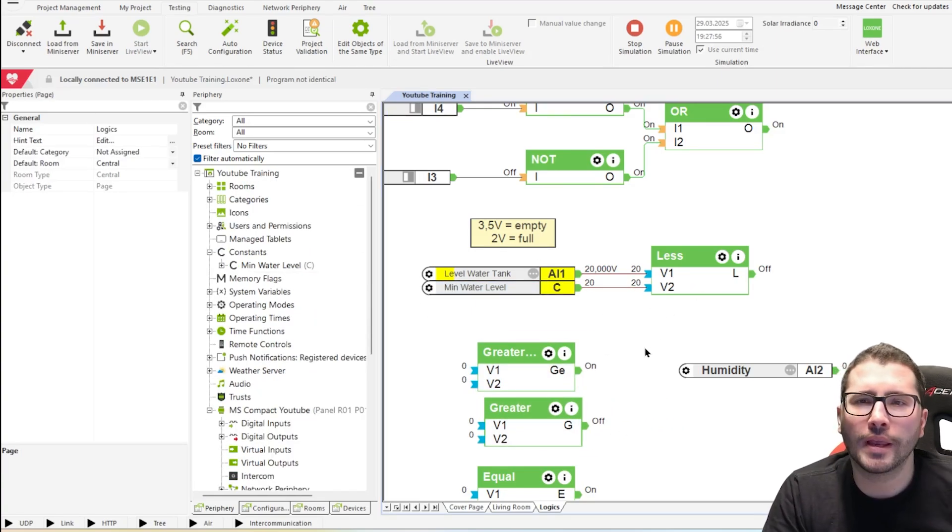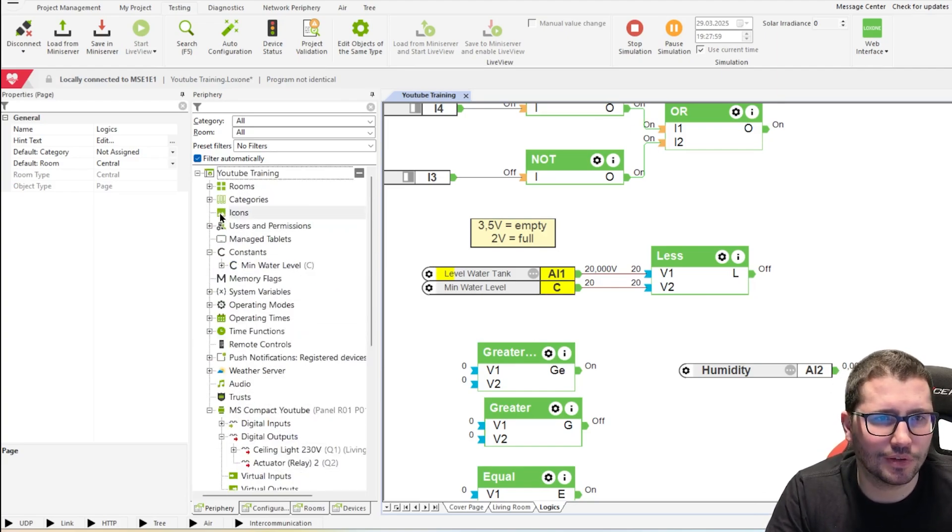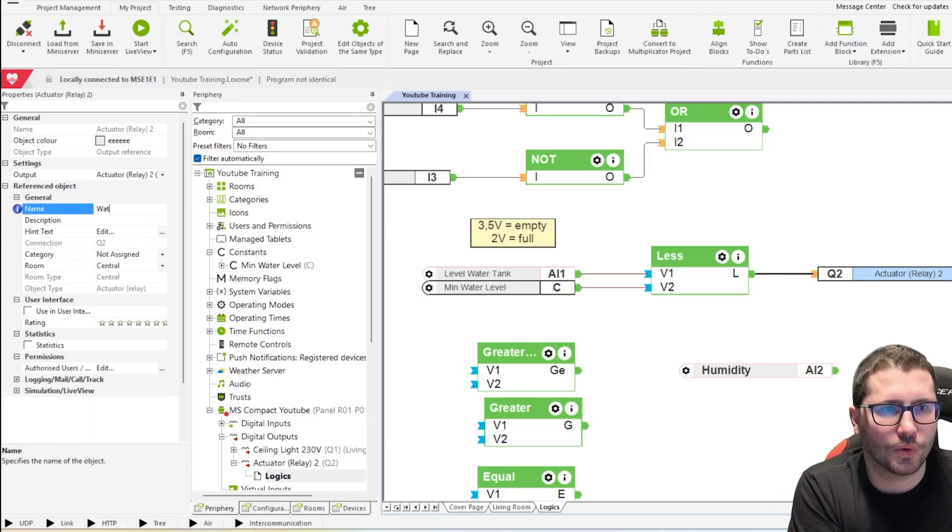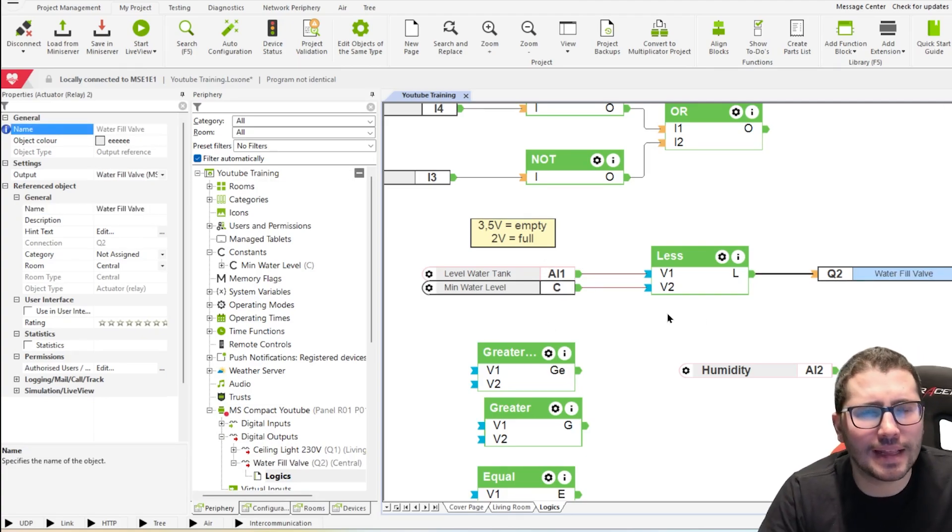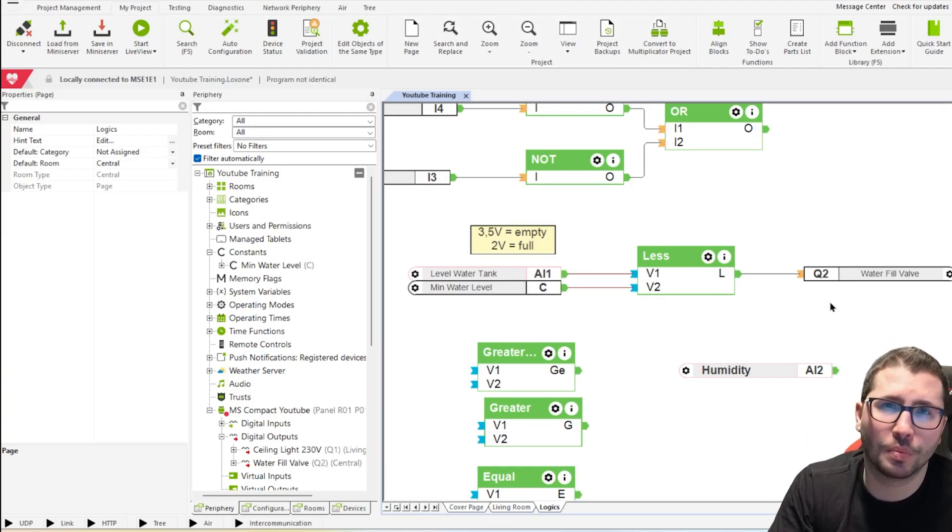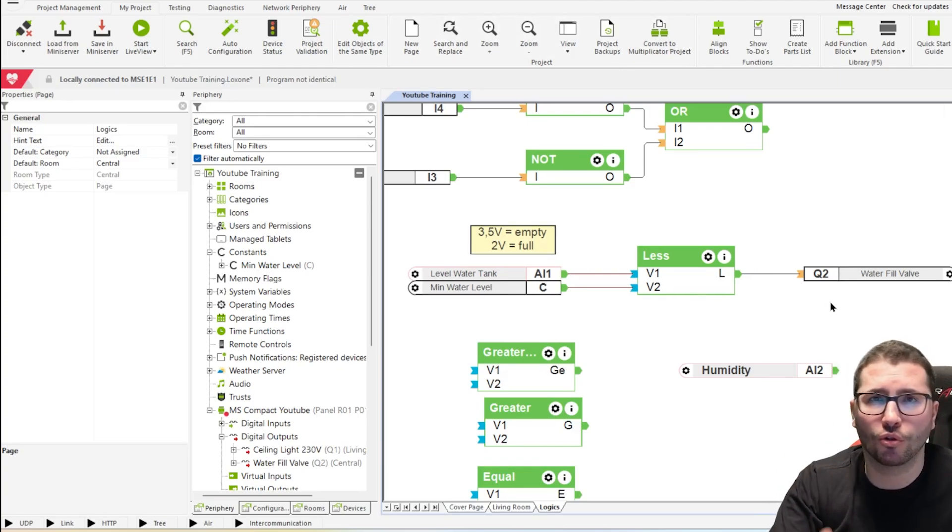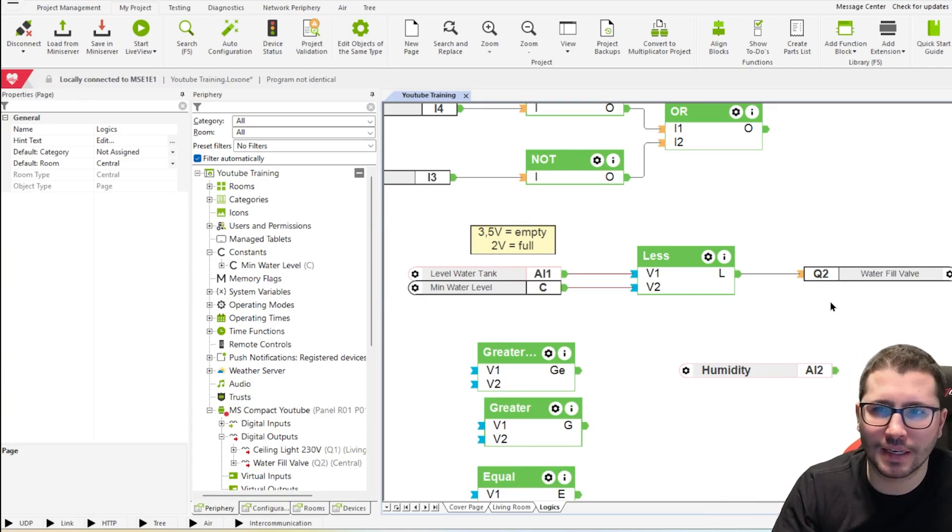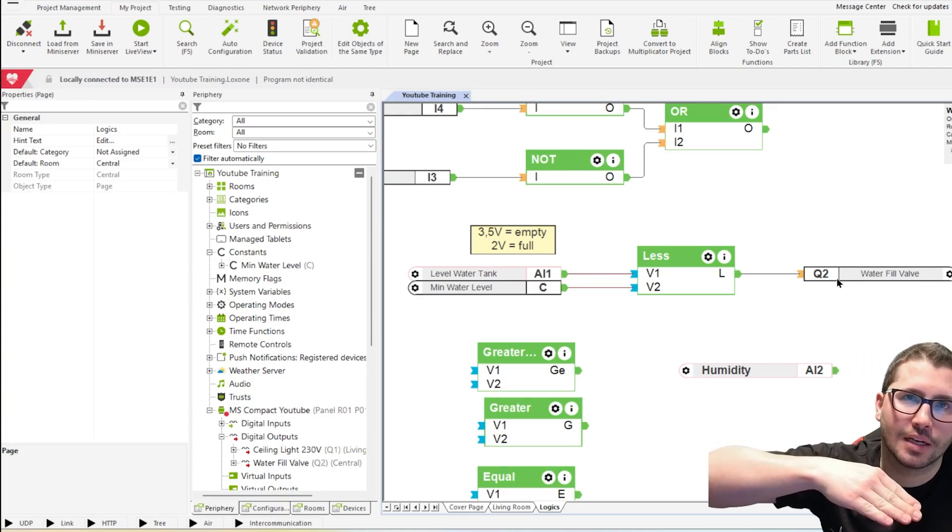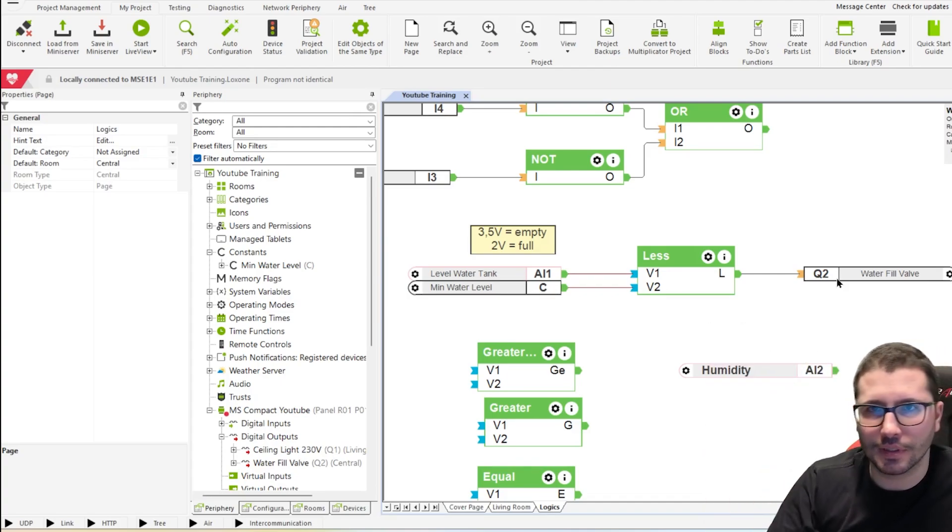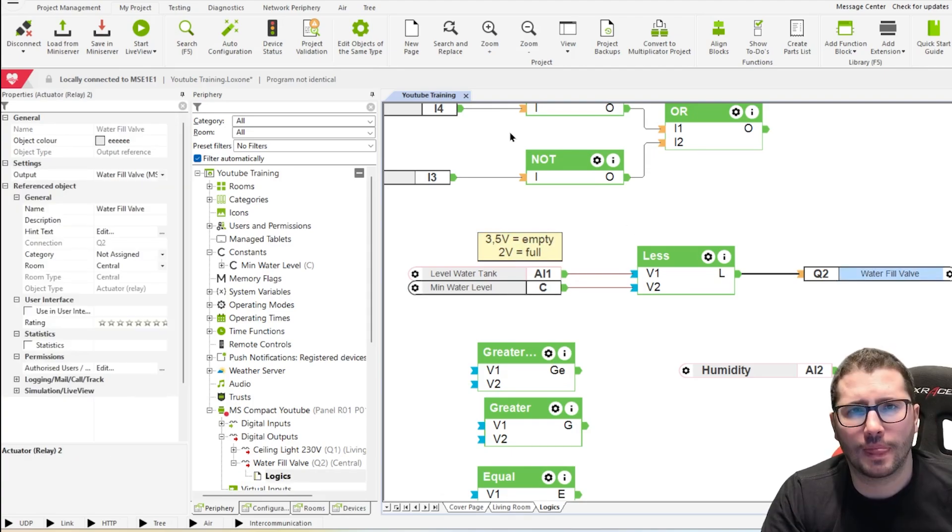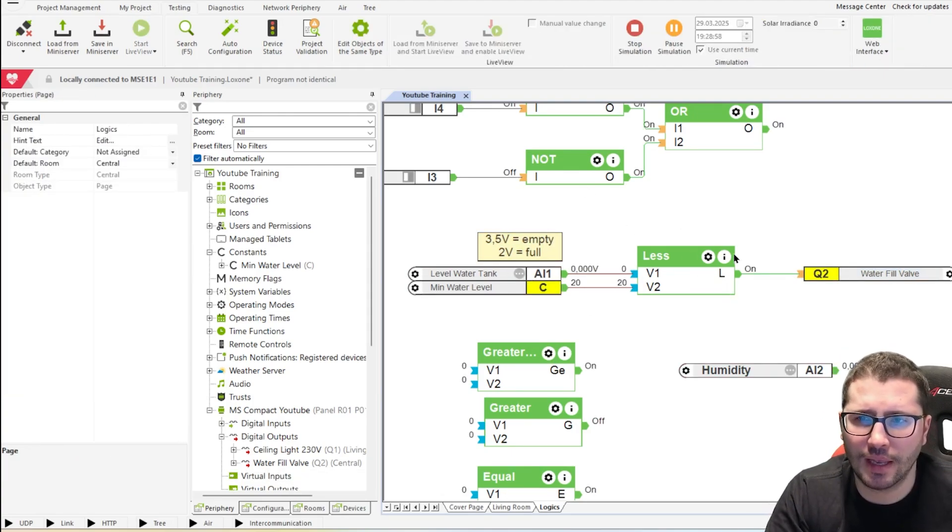So we could now say we have a valve, a magnetic valve here. Water fill valve. It's a magnetic valve, maybe 24, maybe 230. I don't know. Just make sure to pick the correct one. Normally closed, normally open with no power closed or open, basically. Because if you have a power loss, then maybe the valve is then with a spring opening. And then there is lots of water wasted without you noticing, maybe.